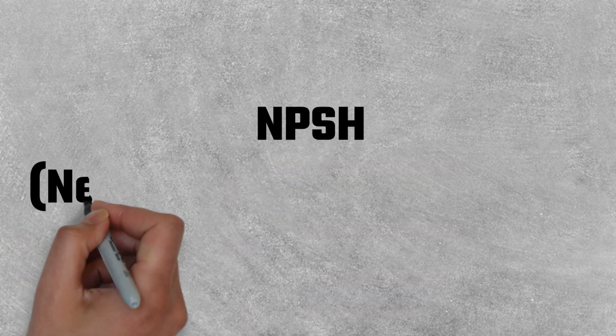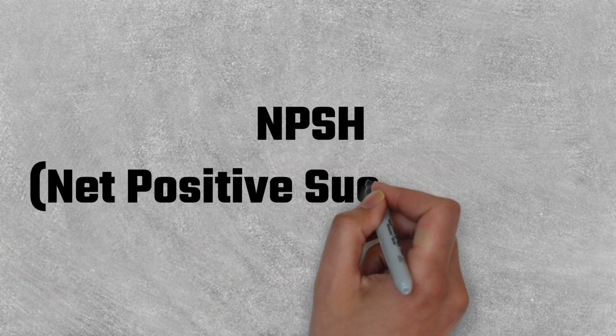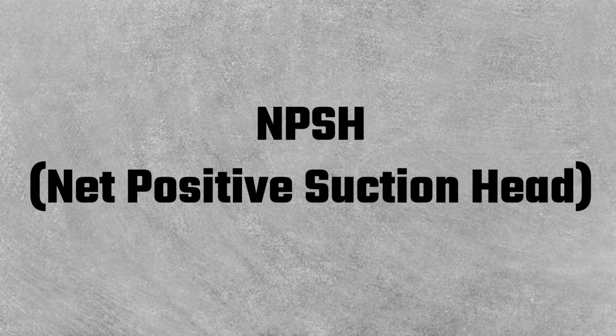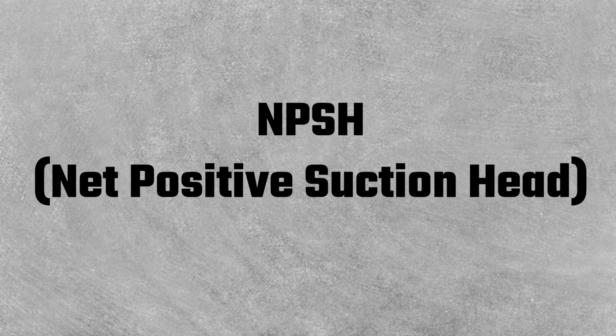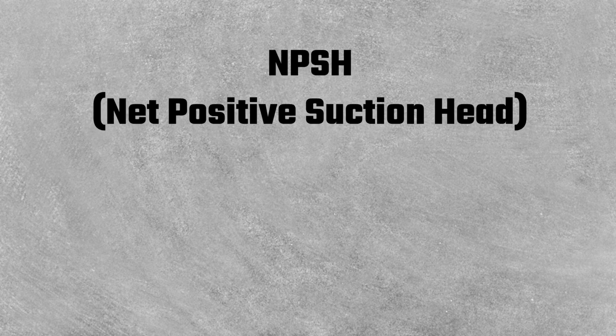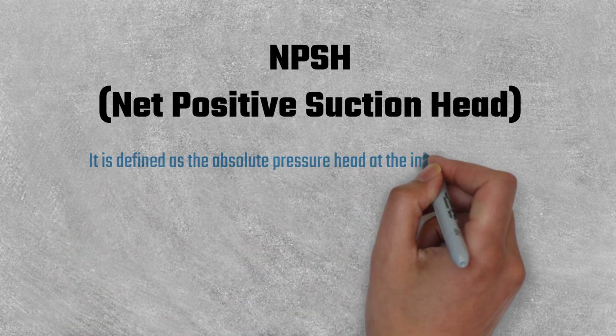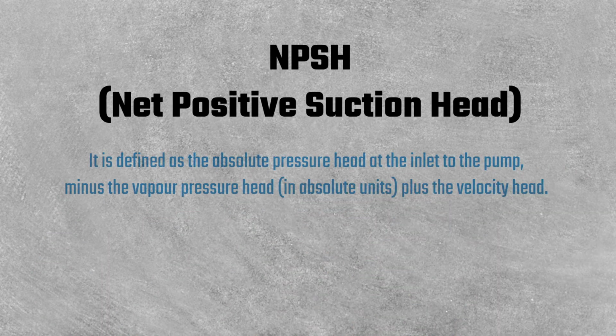The term NPSH, net positive suction head, is very commonly used in the pump industry. The minimum suction conditions are more frequently specified in terms of NPSH. It is defined as the absolute pressure head at the inlet to the pump, minus the vapor pressure head, in absolute units, plus the velocity head.